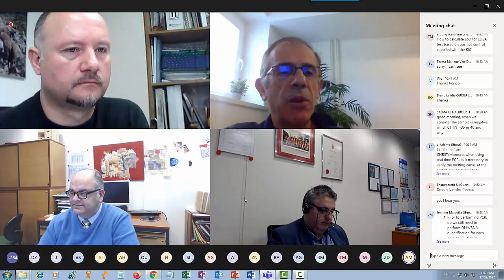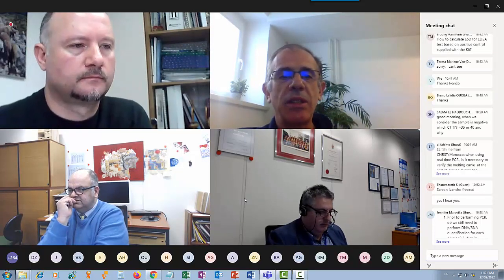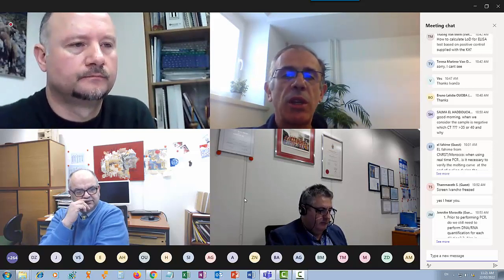Thank you. Okay, thank you very much. If I can add, yes, the end user does not need to test the limit of detection, but in my yesterday's presentation, Ivanchuk has shown a slide with it a few minutes ago. What we were doing when the test was developed here in Zagreb, Croatia, was simply testing different concentrations of the virus applied to the test to see what the detection limit is in terms of virus titer. But this was just during the development and validation of the test, and you don't need to do it in your laboratory.